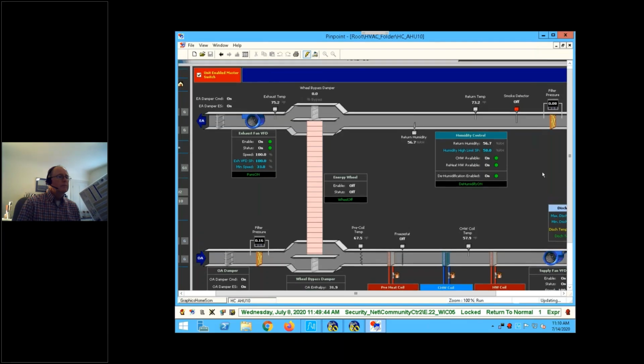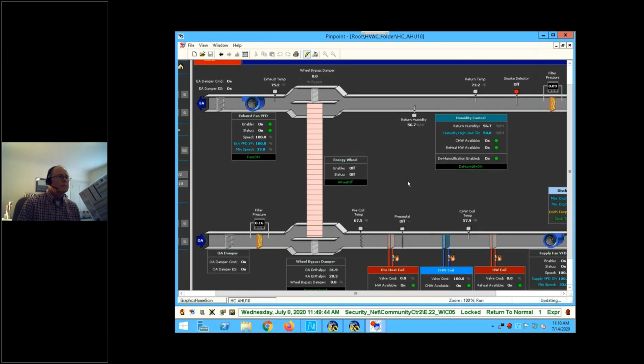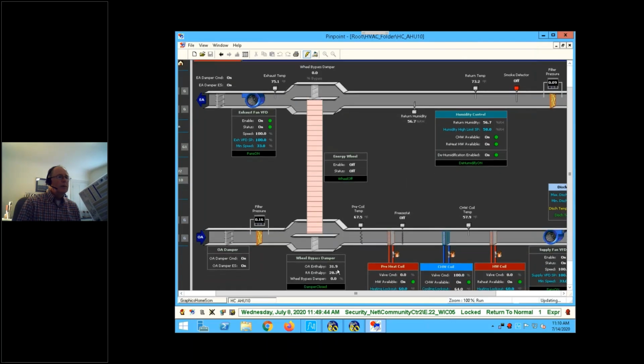And I'm guessing we're not going to economize based on that high humidity. No, we wouldn't economize necessarily at this temperature. However, if there's no need for the wheel to run because we're below the set point temperature, it seems to me that you would normally have some sort of a stop-jog feature, so you're not loading up the wheel.